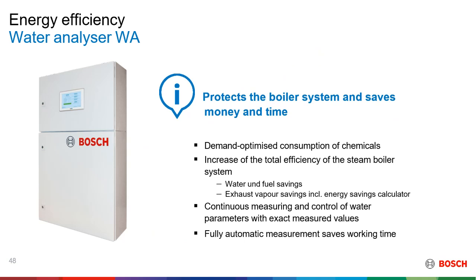Then another aspect of saving potentials is water analysis. So I'll pose another rhetorical question. Do you know the quality of the water that you're using in your boiler? How often do you measure conductivity, TDS, especially pH? So you can have a system where you have continuous monitoring of the water that is flowing into the boiler, and you're able to determine where you have contamination. Might be from the condensate, might be from the feed water tank, and so on.